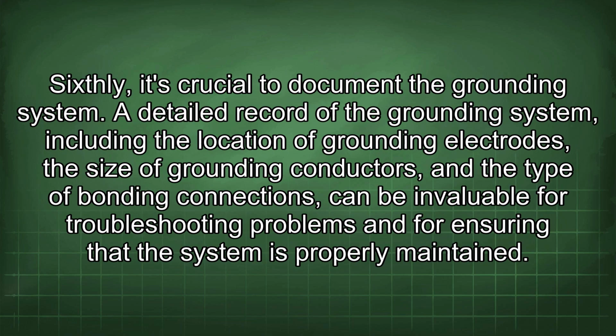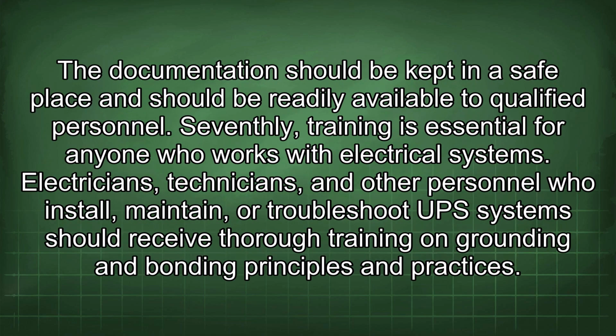Sixthly, it's crucial to document the grounding system. A detailed record of the grounding system, including the location of grounding electrodes, the size of grounding conductors, and the type of bonding connections, can be invaluable for troubleshooting problems and for ensuring that the system is properly maintained. The documentation should be kept in a safe place and should be readily available to qualified personnel. Seventhly, training is essential for anyone who works with electrical systems.